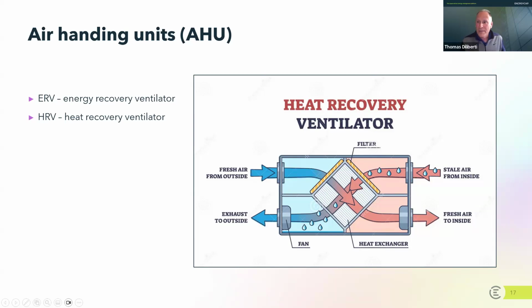If you pay to heat air and put it in the building, you don't want to give it away for free. If that air already has heat in it, as it's passing back through to exit the building, you want to give it a chance to share that heat and put it back into the incoming air. That's the idea of an energy recovery ventilator.